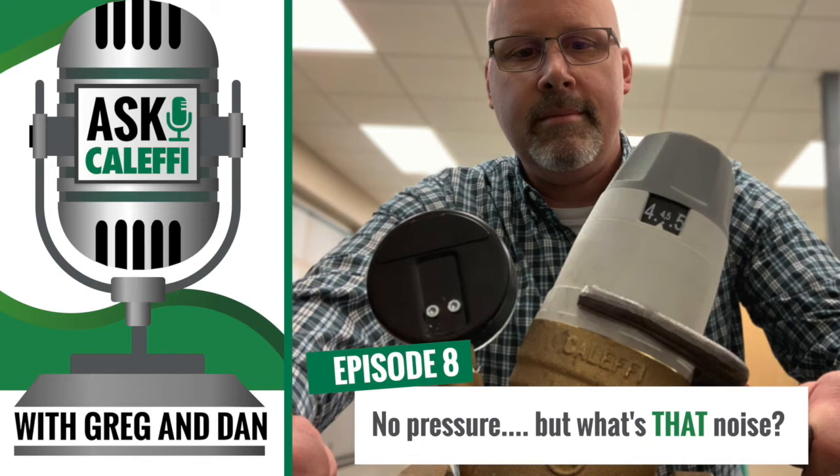Okay, so you've got one inch coming in, one inch going to the home, and you picked a one inch pressure reducing valve. Is this a residential or commercial property? Oh, definitely residential — it's a three bedroom house with three bathrooms and a handful of other things. Just two people live there. Have you gone through the home and come up with a design flow rate that you think you need? Well, I really didn't. I just went with what I saw for piping there.